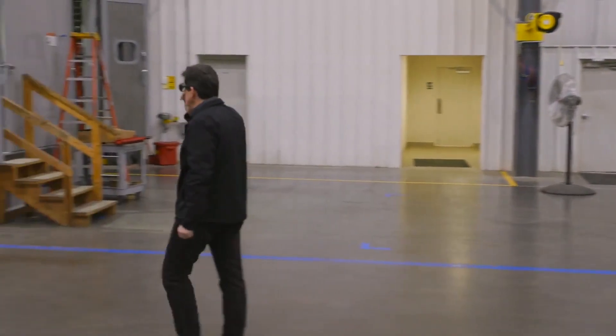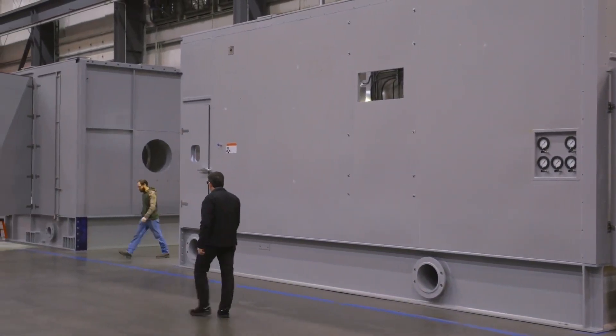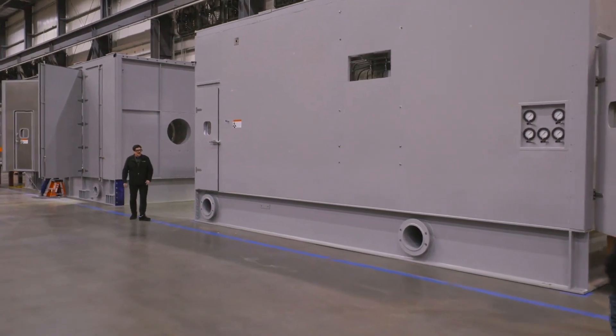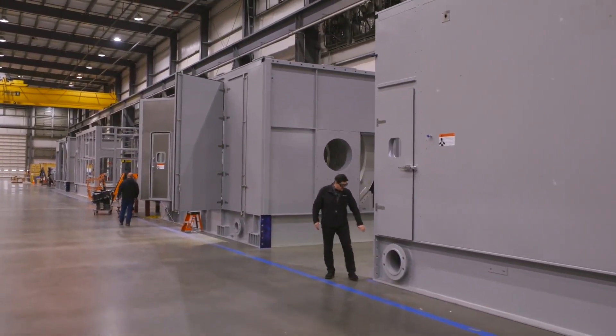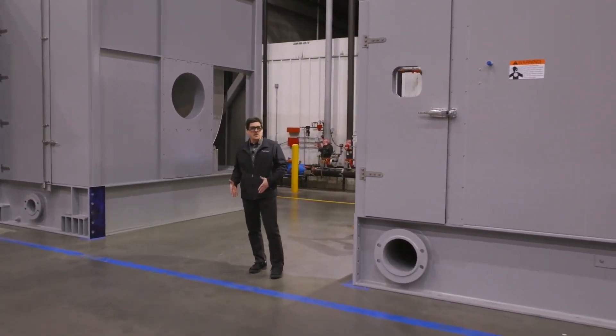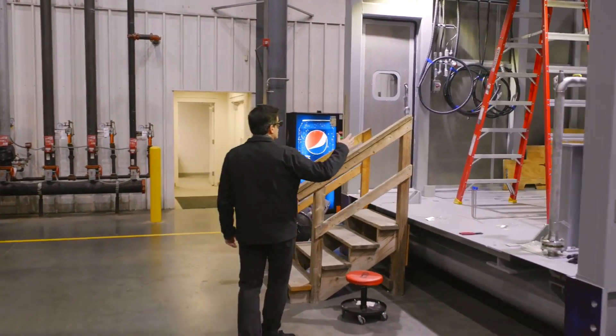Here is a generator package almost done and a gas turbine package. Each generator and gas turbine package are fit up in the shop and serialized on plates so that when those two plates go together, we know it lines out the way it should and we get exactly the alignment we need.